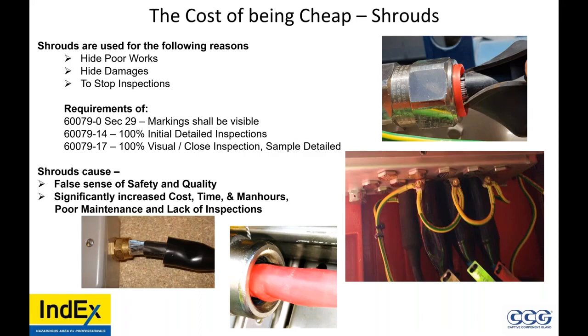But what are the requirements? Well, 60079-0, section 29, markings shall be visible. With a shroud on there, they're not visible. 60079-14, 100% detailed inspection. All glands and accessories shall have 100% detailed inspection. So as per -0, they have to be visible. -14, you have to do 100% detailed inspection.